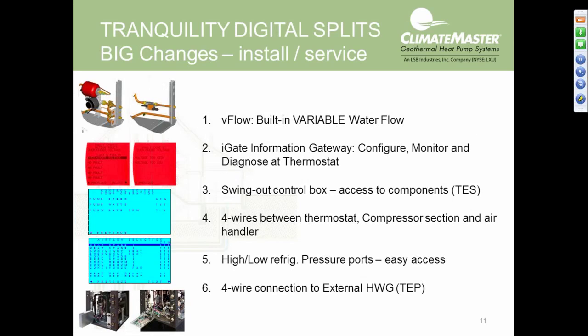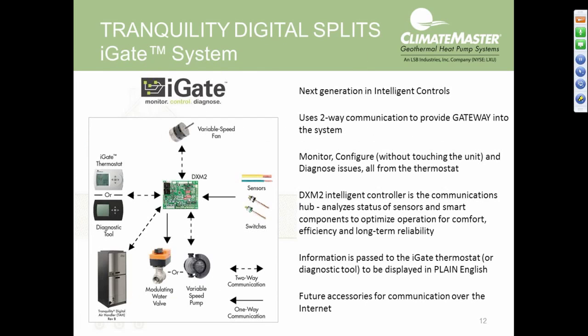Things like the high and low refrigerant service ports are easily accessible right behind the front access door. Once we verify the water side, if we have to get on the refrigerant side, we've got our ports right there, making it easy to do. Obviously on our splits, we're going to be making those connections so that we can properly charge the system, and we have those ports readily accessible. And only on our splits, this is a real nice feature versus what we had before: only a 4-wire connection between the split section and the air handler section. Very nice, especially in a retrofit application where you may not have enough control wires between the two without pulling new wire.